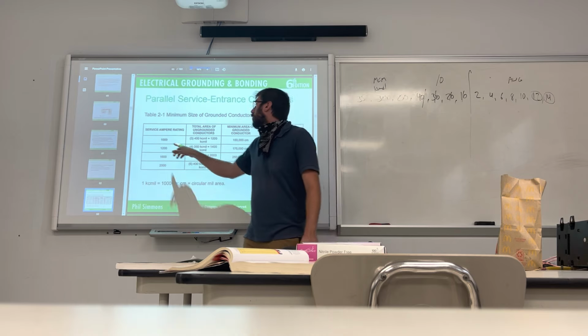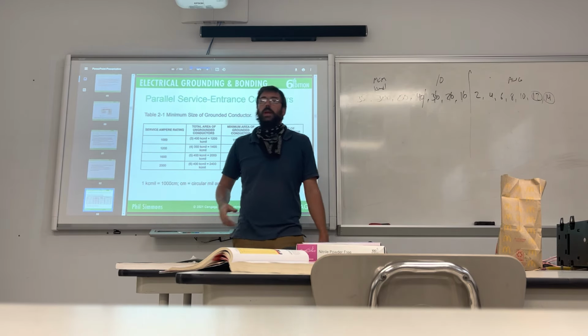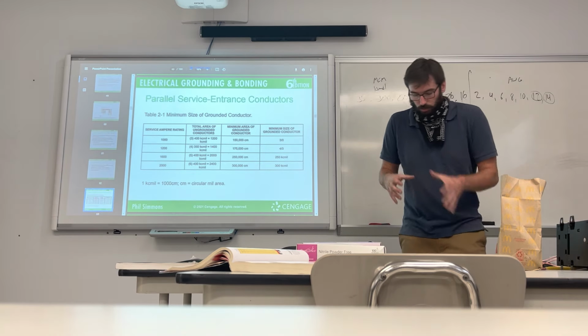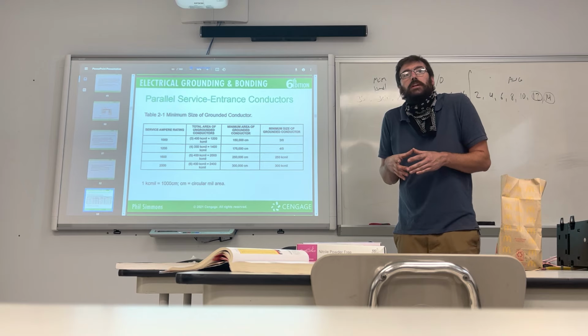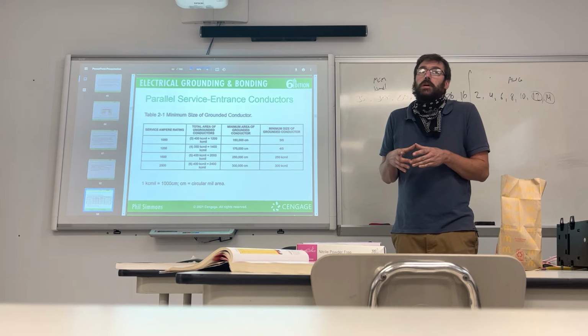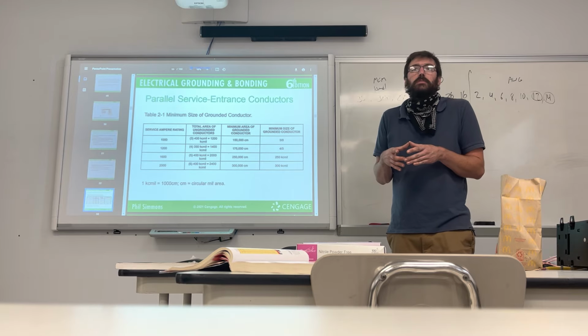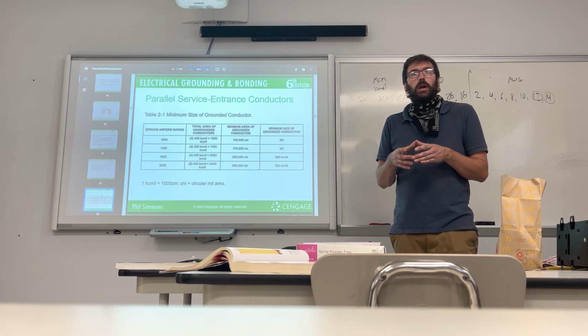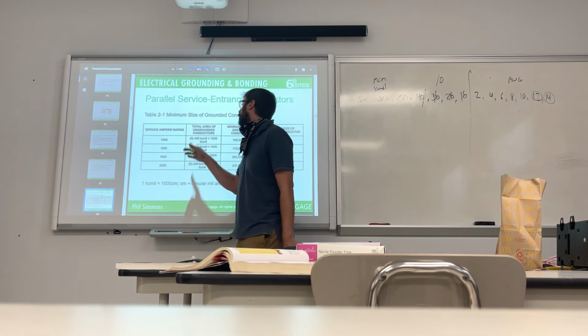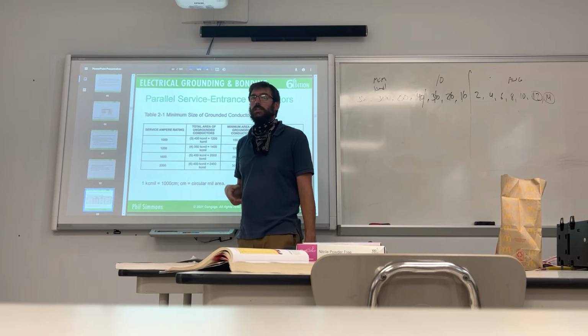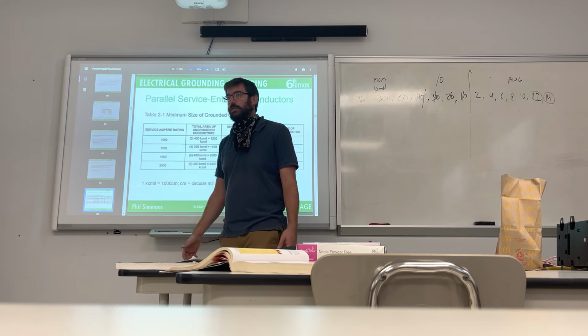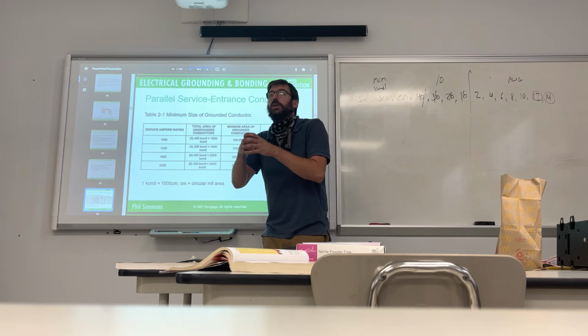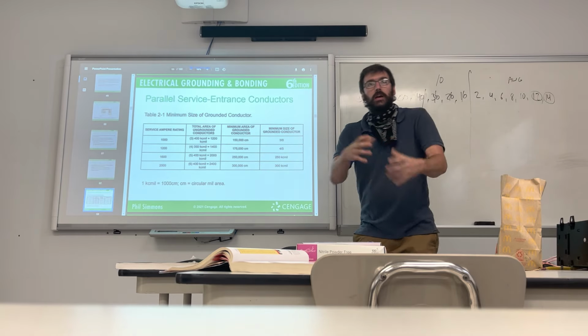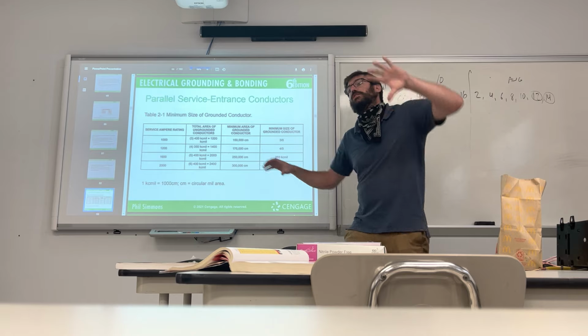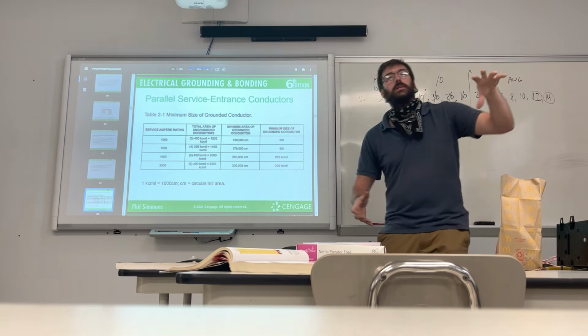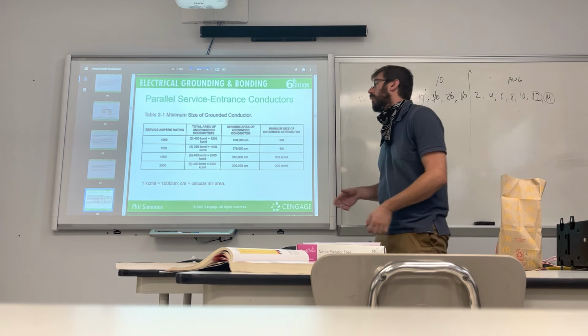So if you run a 1,000 amp service and you ran 1,000 kcmil, the wire would be so huge and unmanageable. And like I said, you have to keep them all in the same piece of conduit. Can you imagine how difficult that would be, bending it, getting the conduit big enough for it? What's more common is to split that up into two or three. So if we have three 400 kcmils, what's 400 times 3? 1200, right? And if you were to add them all together, that would still be well over the amount of copper that's in the 1000 kcmil. But it's going to be way easier for you to bend three 400s than 1000. It's going to be a lot easier to put in the conduit. It's just going to be easier in general.